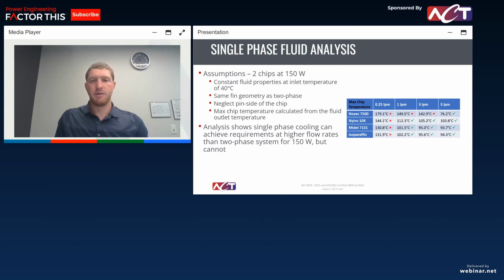And then just kind of a comparison to single phase, looking at the 150 watt, we were able to find a solution at 1 liter per minute for the 150 watt case. But that was greater than the flow rate needed for two phase, and you had greater junction temperatures. And then when we moved to the 900 watt case, you were not able to find a solution at that case. So kind of where we talked about before, there's still places where single phase can be useful, but once you're really increasing those watt densities, those power densities, those heat fluxes, greater than 100 watts per centimeter squared, oftentimes two-phase solutions are going to be one of your only options and going to save you a lot of problems. So I think that's everything I have.